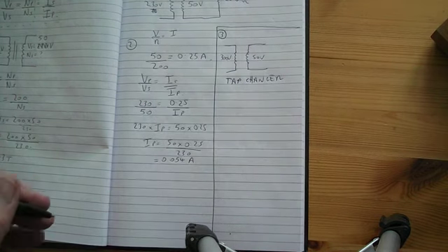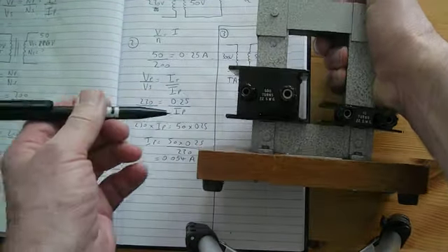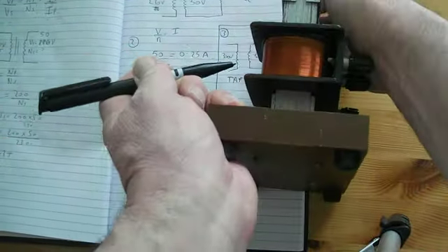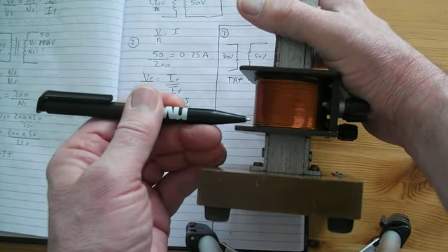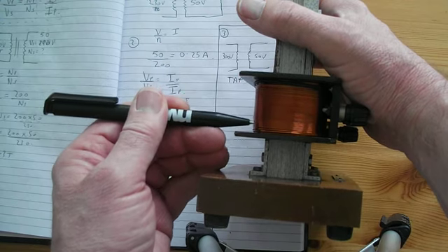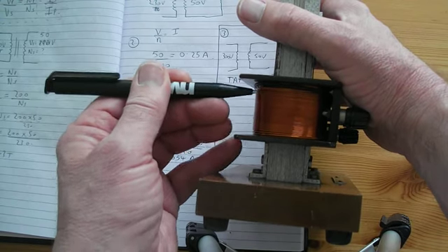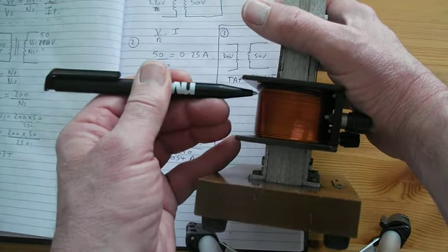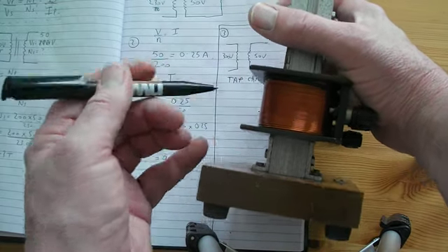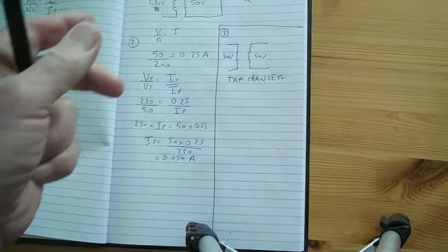Now, a tap changer is an automatic switch which makes contact with the windings, and it moves up and down the windings like that, slightly touching the windings. So it can automatically increase or decrease the number of turns on the transformer by making contact with more or fewer turns. It's called a tap changer.